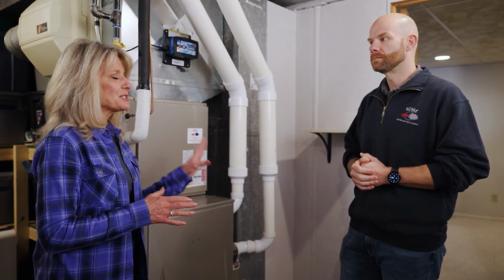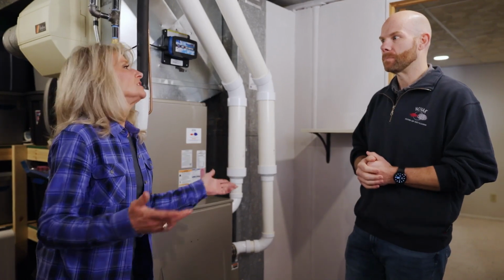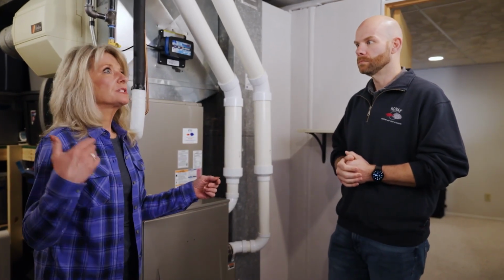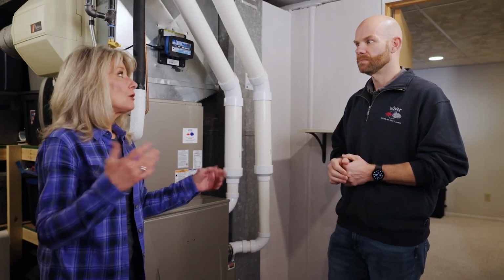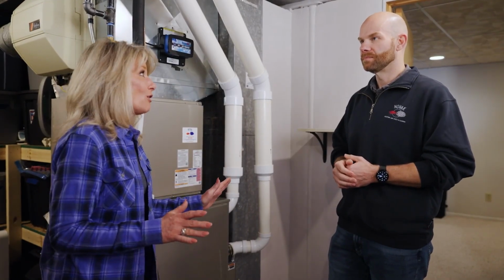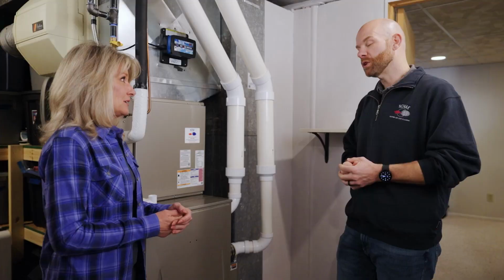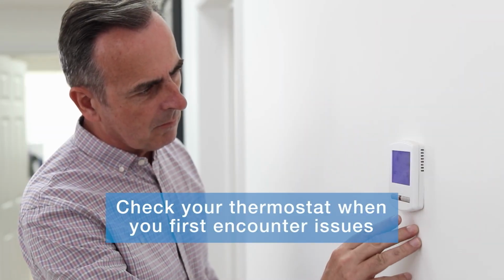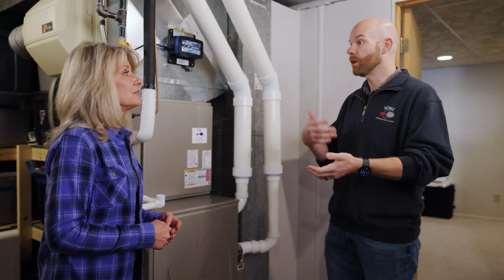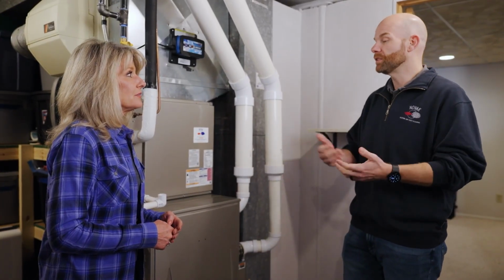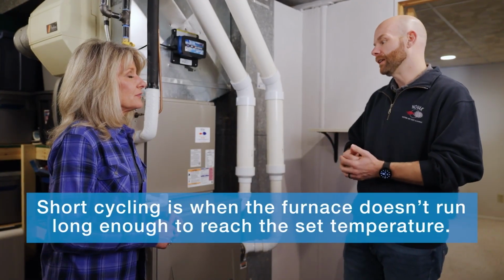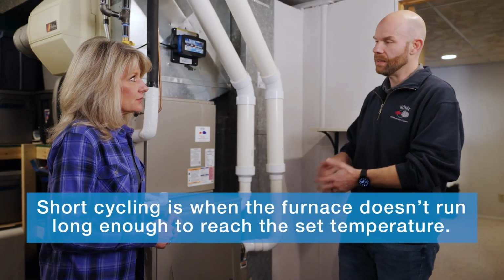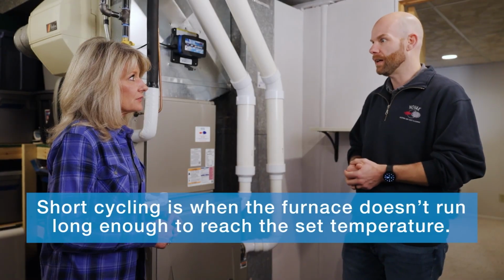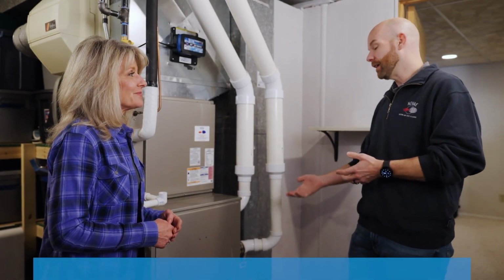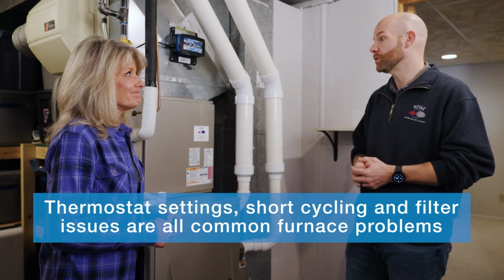And my last scenario: I'm watching TV, say, and my furnace keeps cycling on and off, or it doesn't turn off at all. What does that mean? It could be a couple of factors. Your thermostat could be set to on, so it's just running that blower all the time instead of auto, which cycles it during the heat cycle. If it's short cycling, that could be a more involved issue with the internal components of the furnace. Again, it could be the filter as well, so I'd also check your filter.